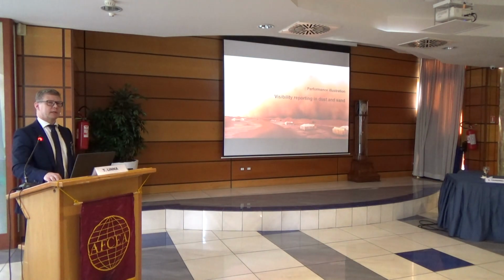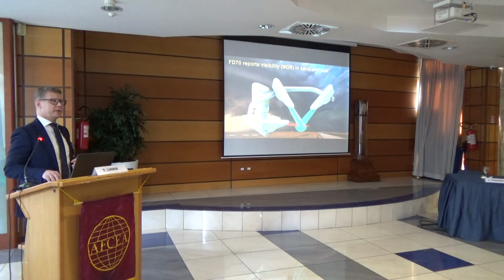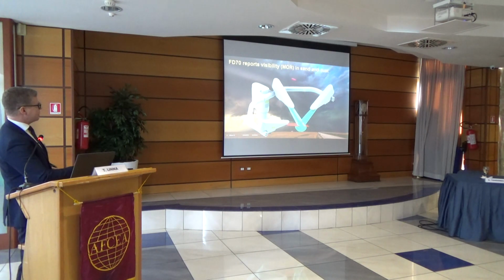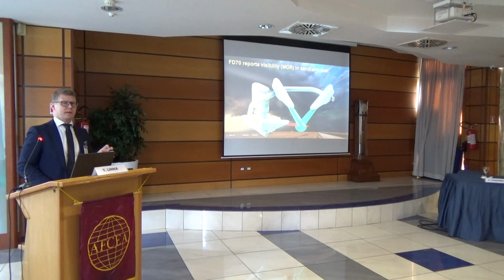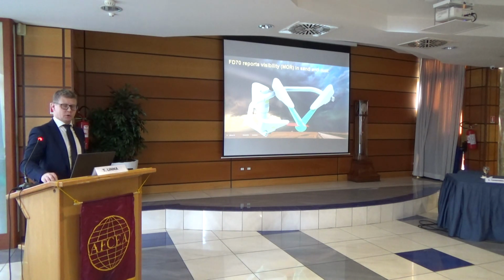I want to mention that in addition to this freezing conditions calculation, we are now able to identify sand and dust in the air, and use a specific algorithm with the help of an additional side receiver to identify sand and dust, and then calculate MOR in sand and dust obscuration.